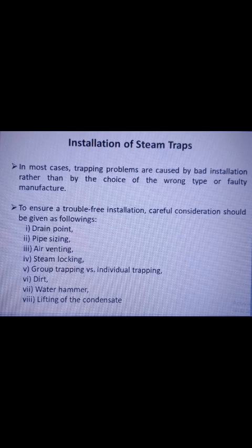Next one is water hammer. A water hammer in a steam system is caused by condensate collecting in the plant or pipework, being picked up by the fast moving steam and carried along with it. When this collection hits obstructions such as bends, valves, steam traps or other pipe fittings, it is likely to cause severe damage to fittings and equipment and result in leaking pipe joints. The problem of water hammer can be eliminated by positioning the pipes so that there is a continuous slope in the direction of flow.